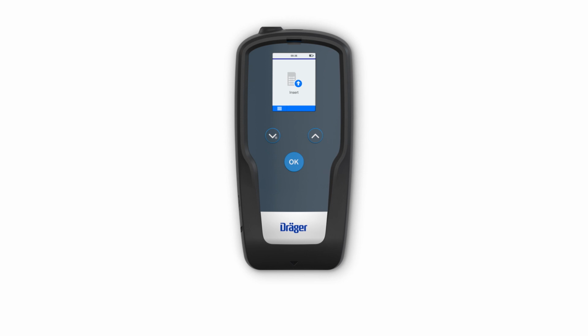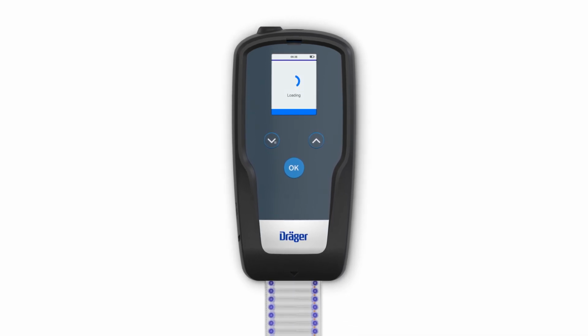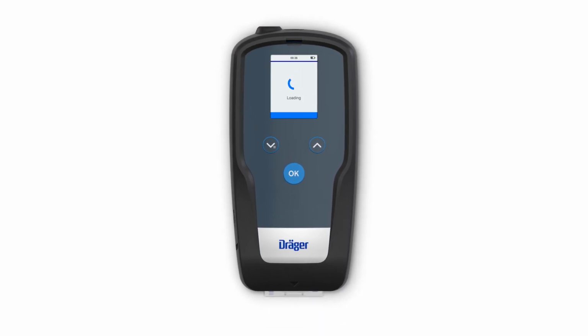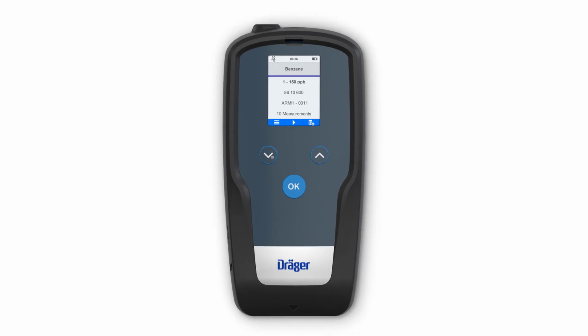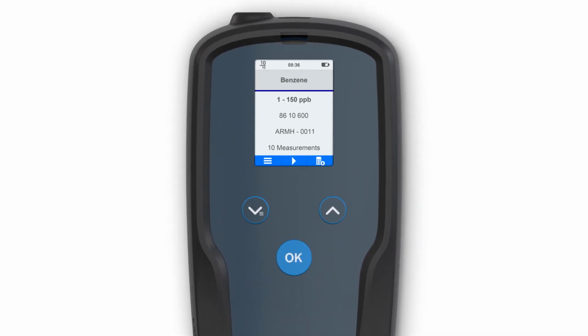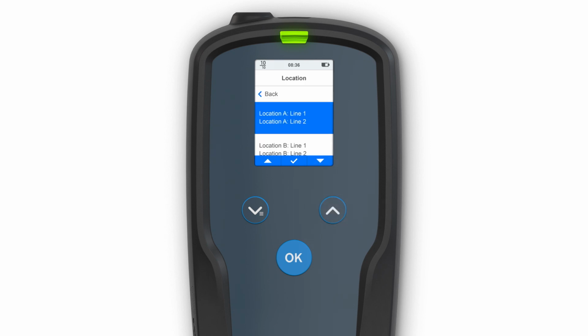Simply insert the correct microtube. The automatic drive carefully draws the microtube in and positions it. Use the 3-button control and 2.4-inch color display to control the test sequence. The green LED and display indicate when the test is complete. You can store the test result, location, and time in the internal data logger and read it later using the Dräger CC Vision software.